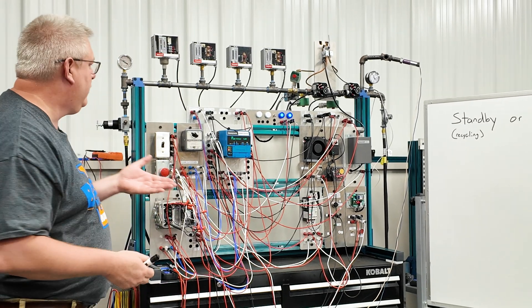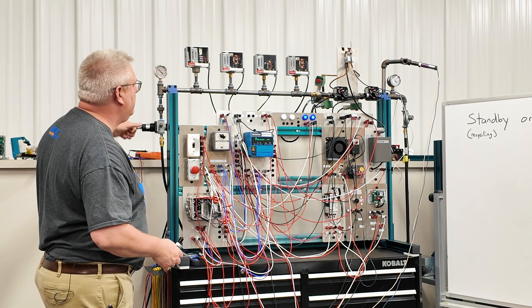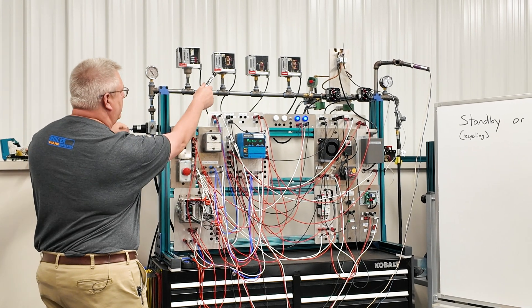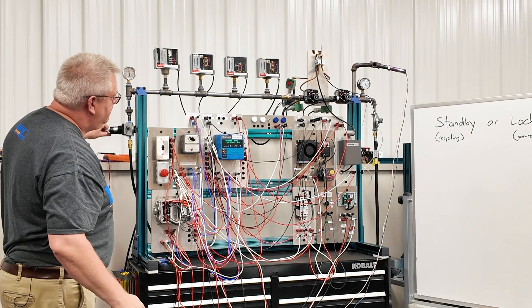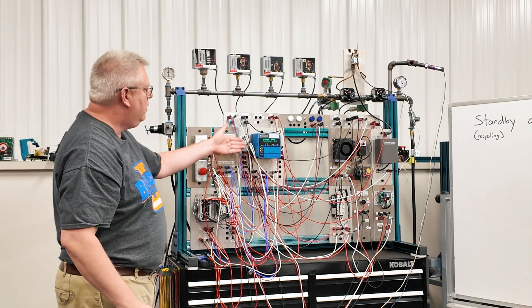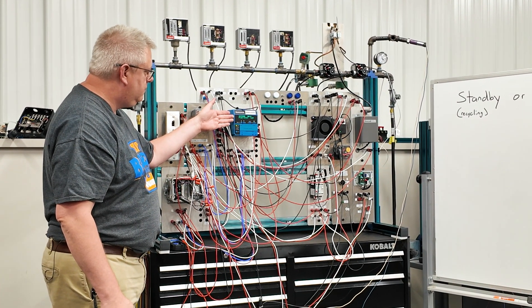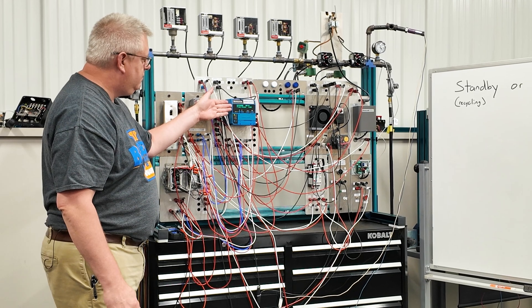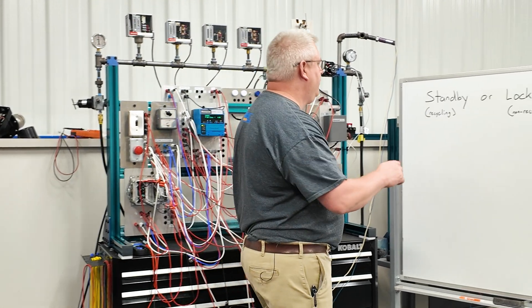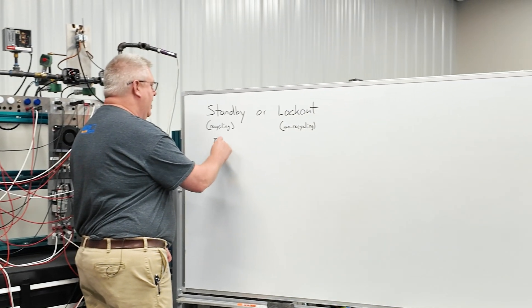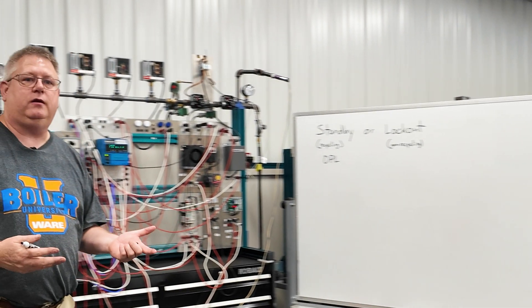I'll demonstrate that by tripping this boiler on high steam pressure. I'm increasing the pressure — we're going to trip on this switch. There, we've shut down. We've gone to post purge, and then standby. So our operating pressure limit, OPL, is in our standby circuit.